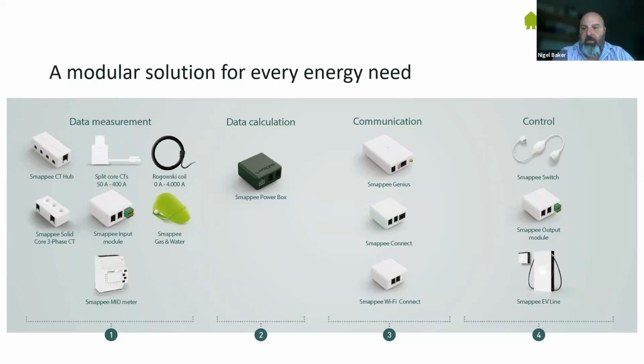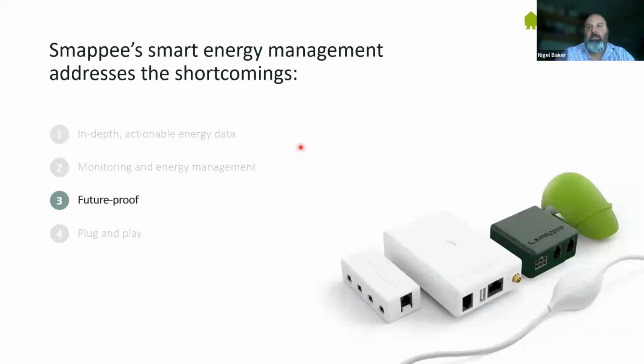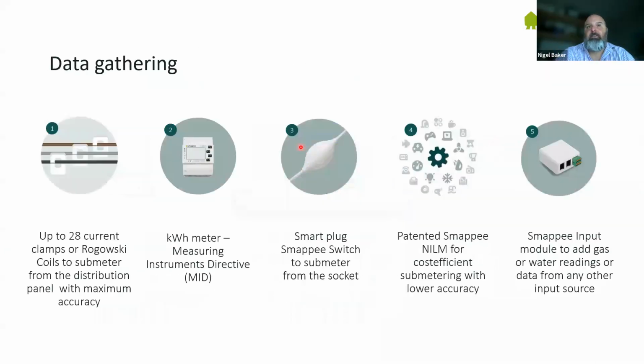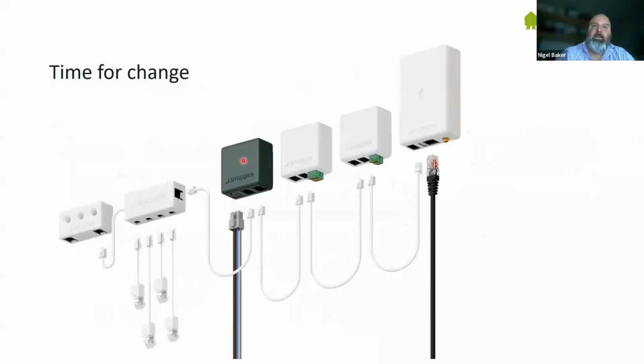Can I connect all Smappee devices to only one Genius device, and what is the maximum allowed distance? Okay, very simply, let me go back to my other slide here. Sorry guys, I'll be there. So the power box, the last current transformer can be 100 meters away from the power box, and the Genius can be 100 meters away from the power box too. This is an RS485 bus, a powered 485, so you can have 100 meters away.